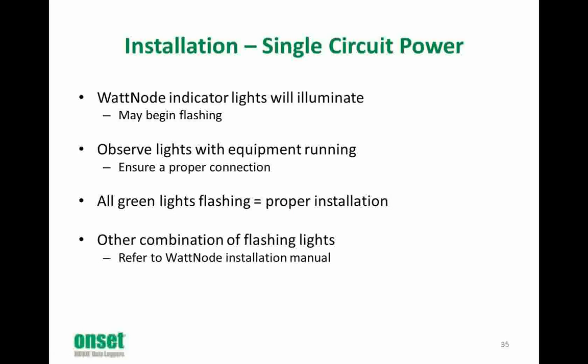Once all the connections are made, the watt node indicator lights will illuminate and may begin flashing. To ensure the watt node is connected properly, we observe the indicator lights with all the equipment running. If all three lights are flashing green, we're in good shape. If the lights are flashing red or yellow, we must refer to the watt node installation manual for proper troubleshooting. If the equipment is not running, it is normal to see the green lights on or lights flashing very slowly, green, yellow, or red.